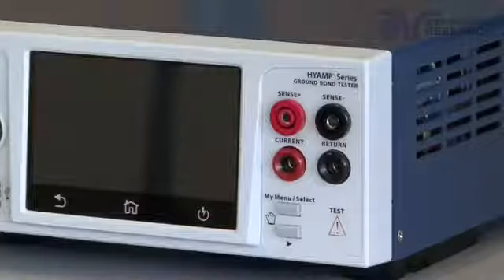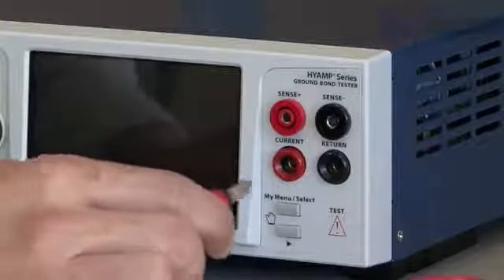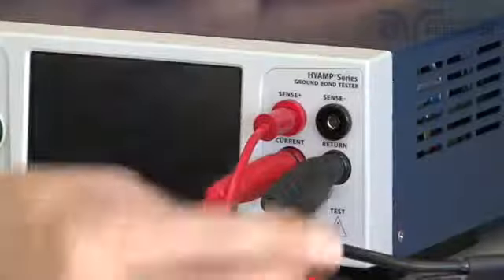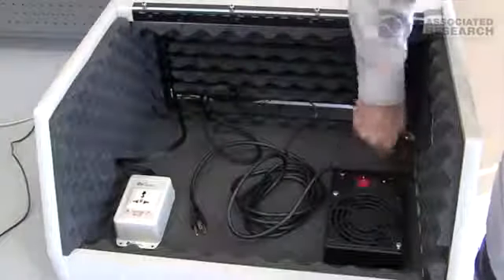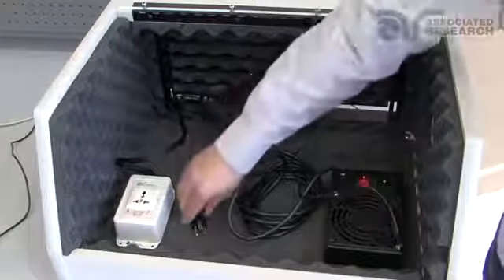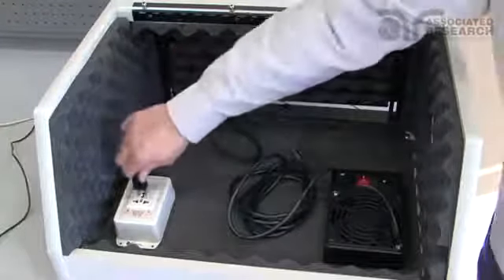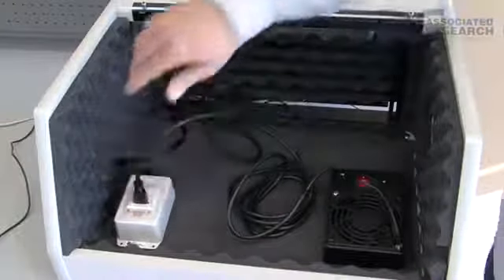First, connect the adapter box to the current sense plus ports on the front panel of the instrument. Then connect the return sense negative lead to the front panel. You can now connect the return sense lead onto the ground stud or chassis point of the DUT. Then simply plug the three prong cord of the DUT into the adapter box.